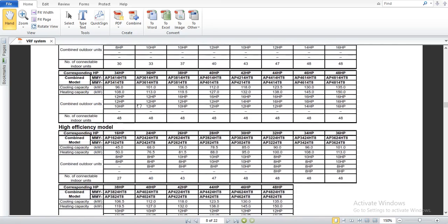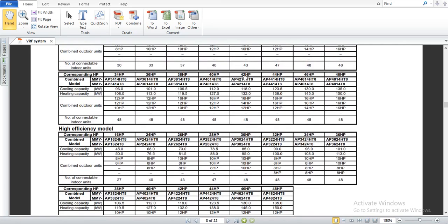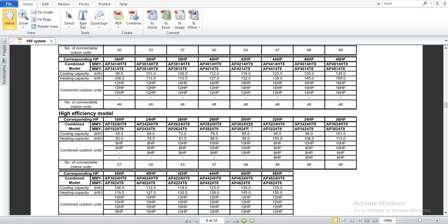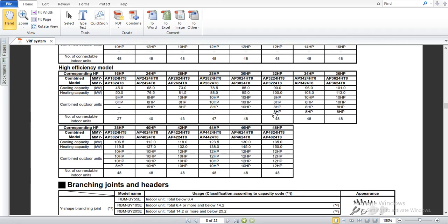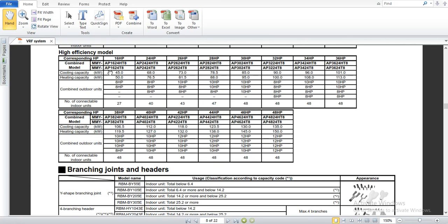For example, a standard efficiency 42 horsepower system is divided into three outdoor units: one is 16 horsepower, another is 14, and the third is 12 horsepower. Make sure to arrange them in order of their capacities — the 16 horsepower unit comes first and acts as the header, and the other two act as followers, as I already explained in my first video. Similarly, if you have a high efficiency model, you can select your outdoor unit from this table.